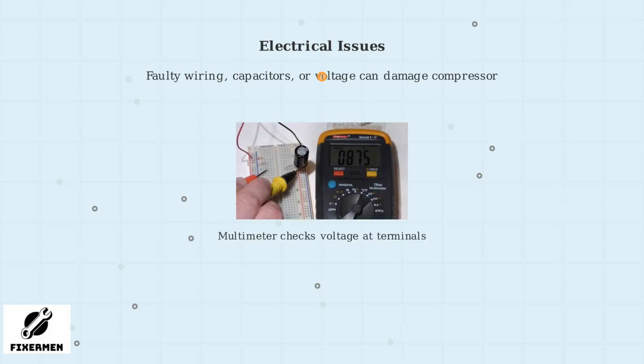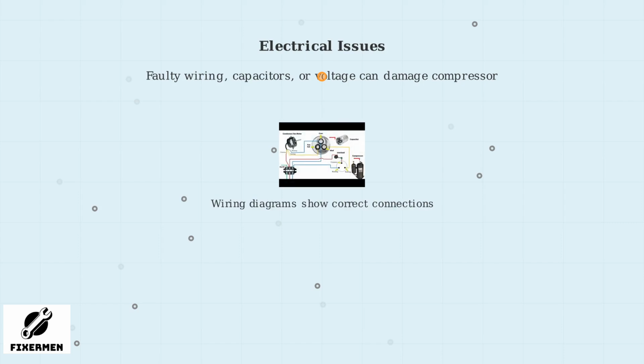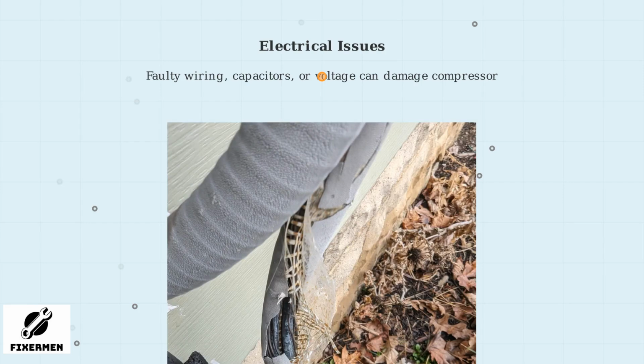Use a multimeter to check voltage levels at the unit's terminals. Wiring diagrams help identify correct connections. Faulty wiring or loose connections can cause voltage drops or shorts. Damaged insulation or exposed wires can lead to shorts and compressor failure. Regular inspection prevents these issues. All electrical repairs should be performed by qualified technicians. Incorrect fixes can create safety hazards or void warranties.